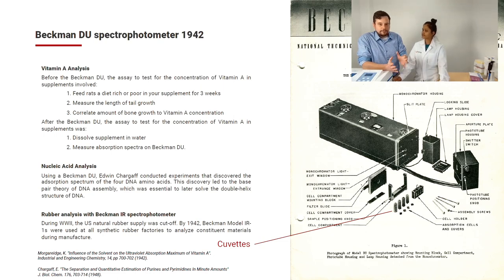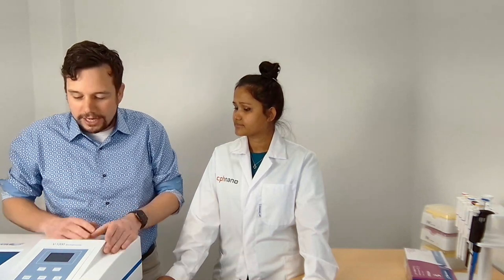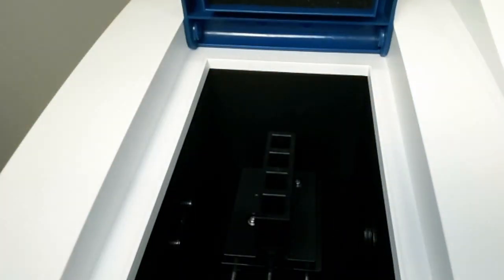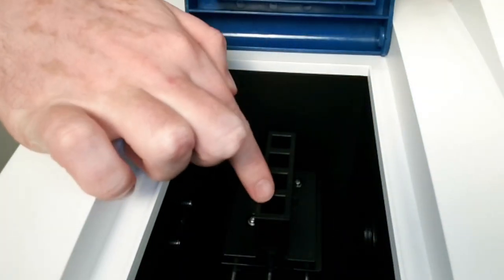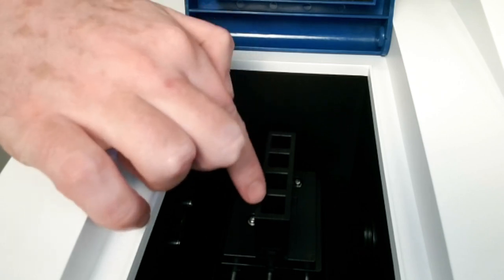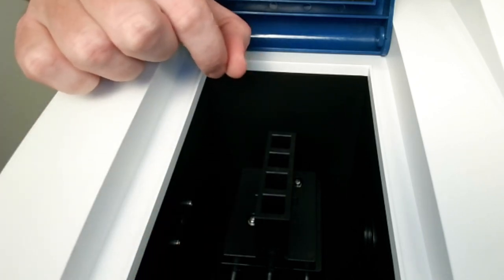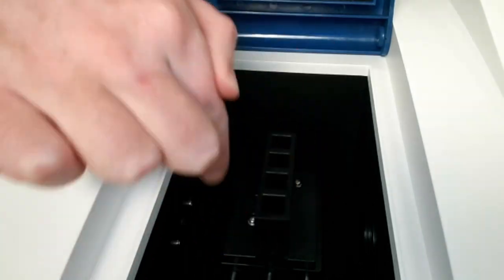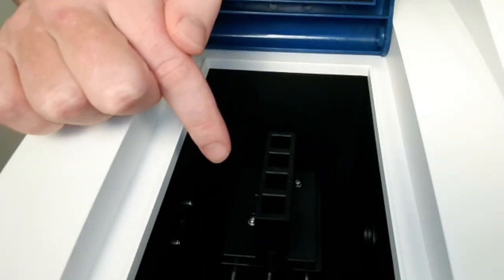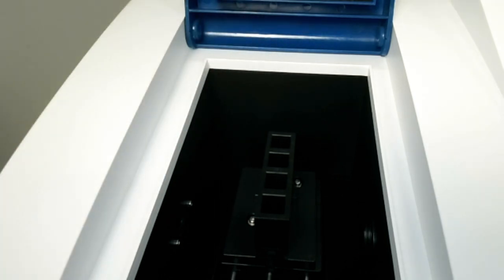In a more modern perspective, this is the VWR 1200 collection lineup instrumentation. If I open up the inside box, you can see the four cuvettes sitting here — the same design as in the original Beckman DU spectrophotometer from the 1940s. We can see how we are still shifting the cuvettes across. The main difference is we have more space around the cuvettes to manage stray light, but otherwise a modern spectrophotometer like this is heavily inspired by the technology of the 1940s.